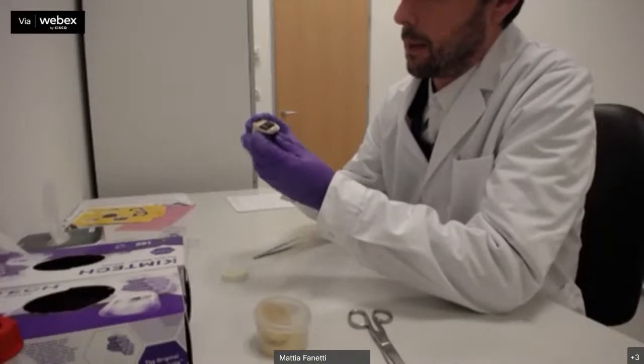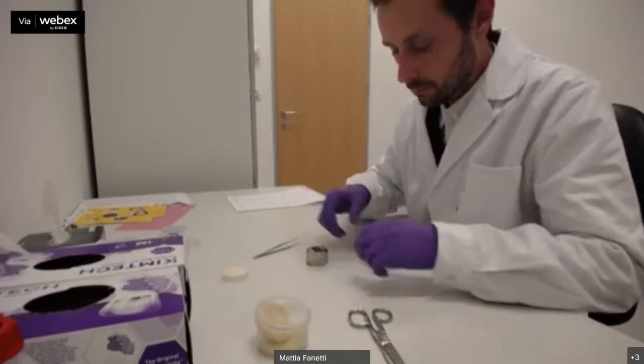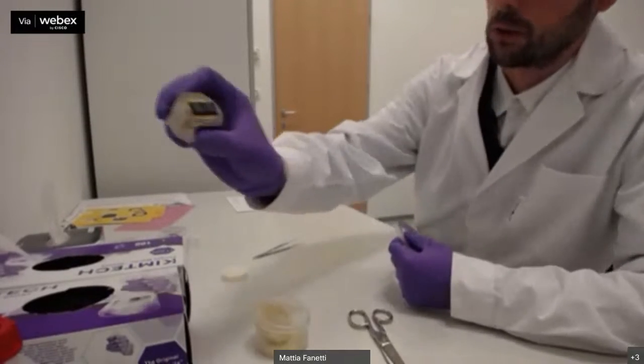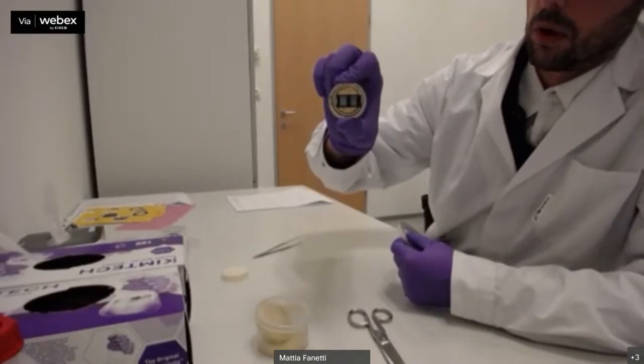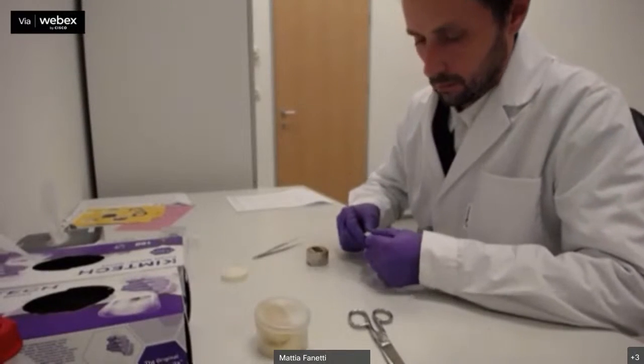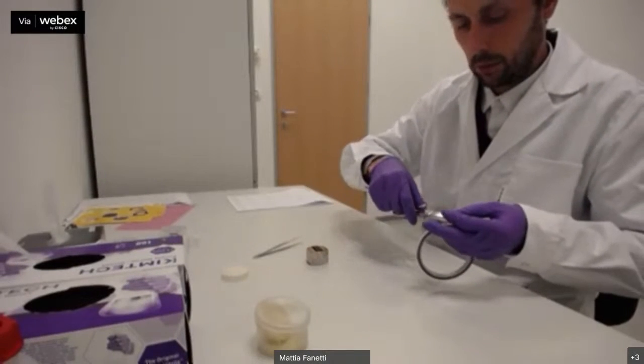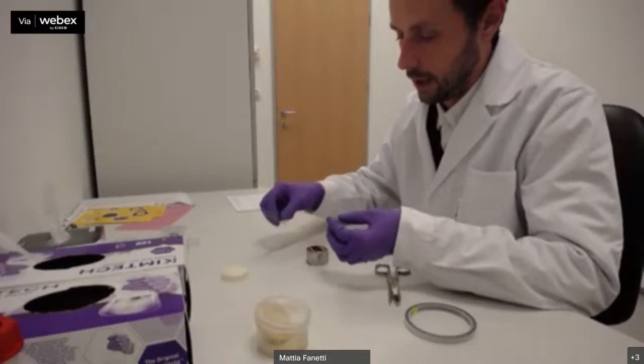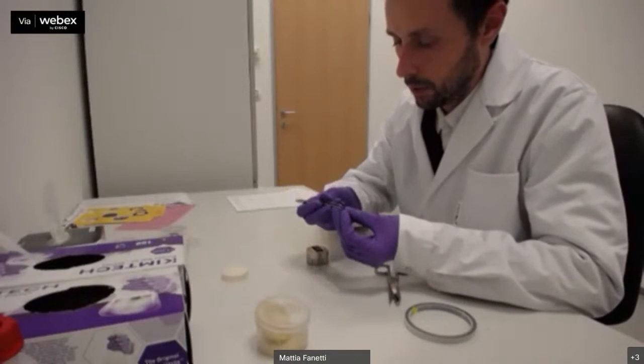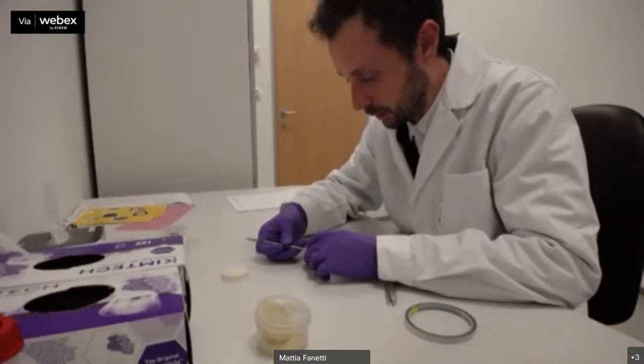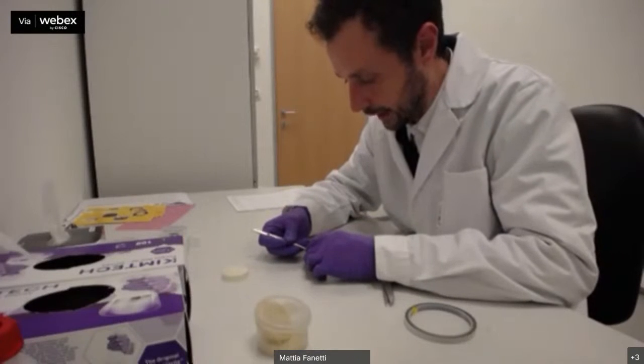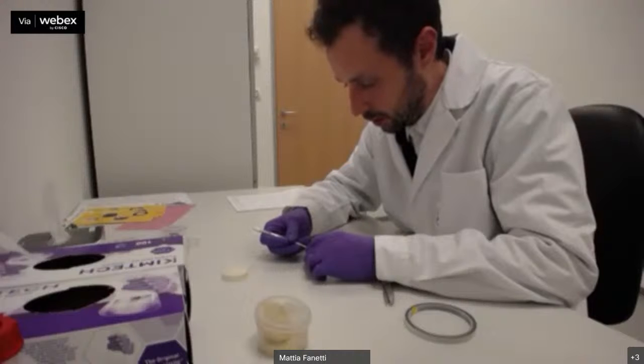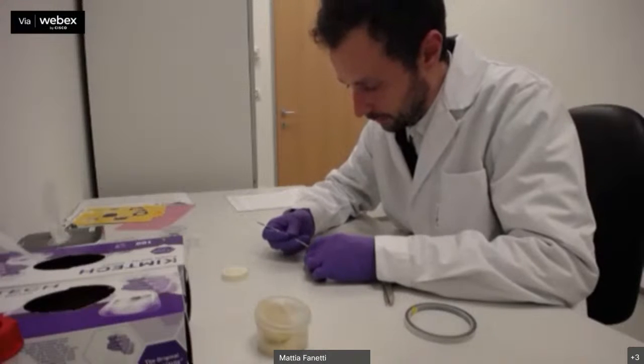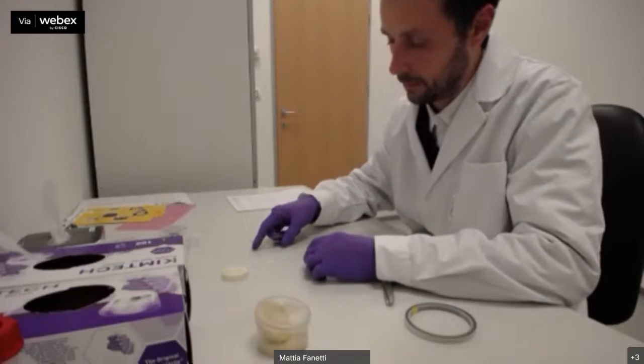So I just fixed the sample on the sample holder with the carbon tape. Can you see the two samples? Yes. Okay. Now I put some additional carbon tape on the side in order to ground the sample surface to the sample holder body, so that the current can easily flow from the sample surface toward the ground of the system. Okay.